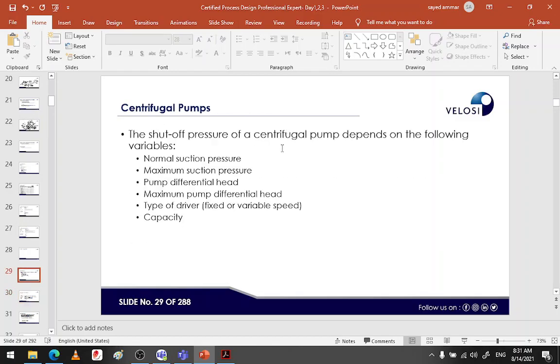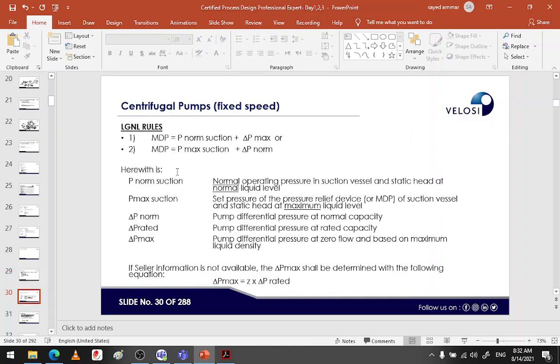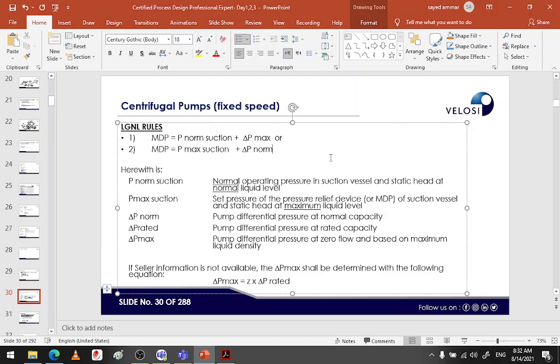The shut-off pressure of a centrifugal pump depends on the following: normal suction pressure, maximum suction pressure, pump differential head, maximum pump differential head, type of the driver (if it's fixed or variable speed), and the capacity of the pump. Maximum design pressure equals the P normal suction plus delta P maximum, which is what the pump can deliver. P normal suction is the normal pressure in the suction vessel and the static head at normal liquid level.